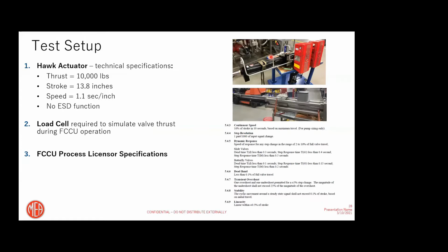So we basically generated a test unit, which has the technical specification of thrust developing 10,000 pounds, stroke 13.8 inches, and speed 1.1 seconds per inch, and did not have ESD function. This was actually a simulated unit for one of our customers. We built an identical one that he wanted to put on an FCCU slide valve. We wanted to test it and prove to us and to everybody else that we can do that and we could do it properly.